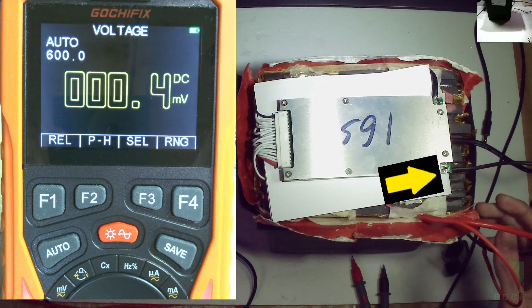The first thing I want to do is probe the BMS output to see if there's any voltage. So I'm going to take my voltmeter probes and probe the positive, and then probe the negative output. You can see I'm only getting 22 point something volts. Notice now, it's hard to keep the probe on there without slipping off, but notice that the voltage is kind of falling. Why is that?